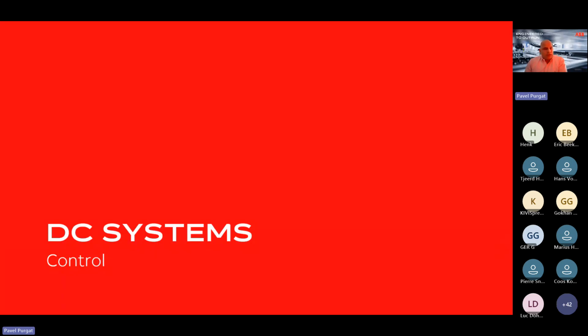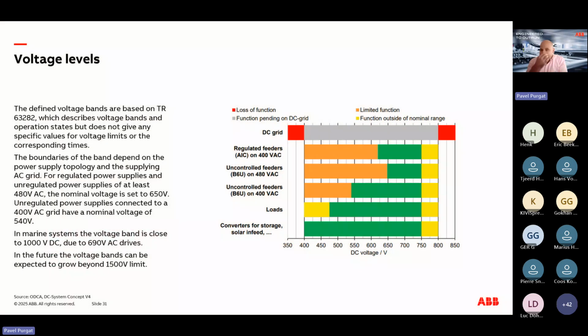A critical aspect of designing a DC system is how we control it. Now, I mentioned that DC is not only about DC, and this is why we usually talk about voltage bands. Here we have an example of a voltage bands defined by ODCA, which is one of the industry alliances looking into DC. You can see that different devices connected to the DC grid can have different voltage bands in which they must provide the full functionality, where they can provide limited functionality, and where they must disconnect.